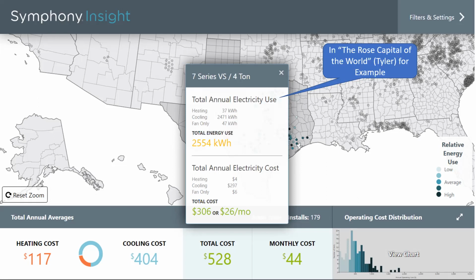What about a house like mine, with a 3-ton unit upstairs and a 4-ton downstairs? For a 2-story application, would you look at two different air handlers, or how would you do a split system? One funny thing is geosystems come in 6-ton units for some reason, while typical residential air source units only go up to 5 tons. You could do a 6-ton packaged unit where your downstairs unit is, connect the two, and zone it. We have digital zoning available.